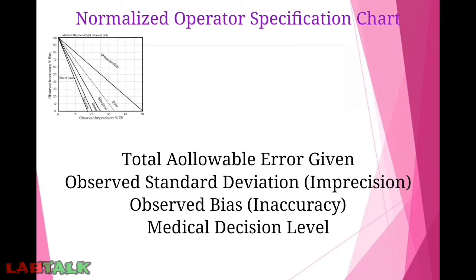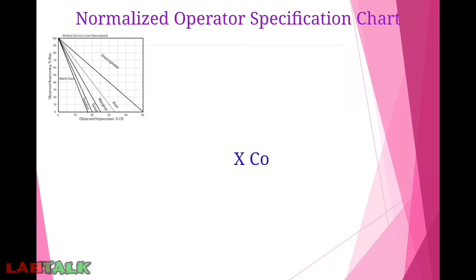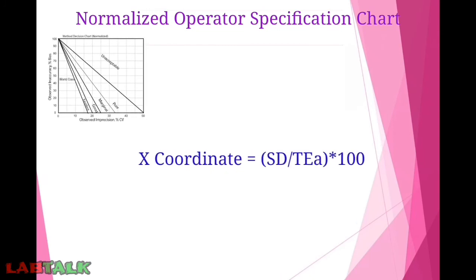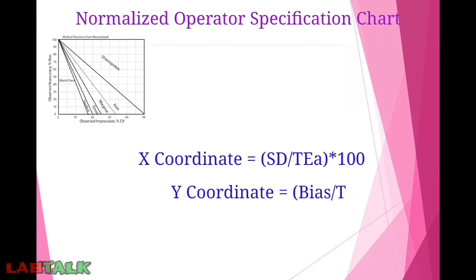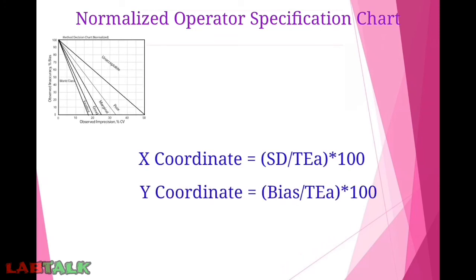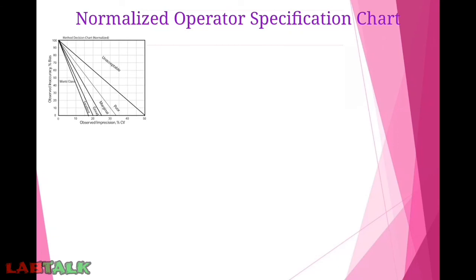The x-coordinate is calculated as: SD divided by total allowable error, multiplied by 100. The y-coordinate is calculated as: bias divided by total allowable error, multiplied by 100. Both coordinates come out as percentages.